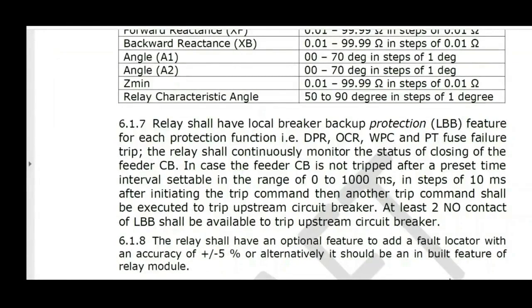Let's see two important concepts. In the specification, we have seen all the protection functions. In the majority of the protection functions, or almost 100% of all the functions, we are using a current-based principle. That is, here CT is one of the basic requirements. For distance, we use both CT and PT. For overcurrent, for WPC and many other things, we are using the current transformer. One big challenge which we face in a current transformer, this is a very, very important concept, is called CT saturation. So let's understand what CT saturation is.